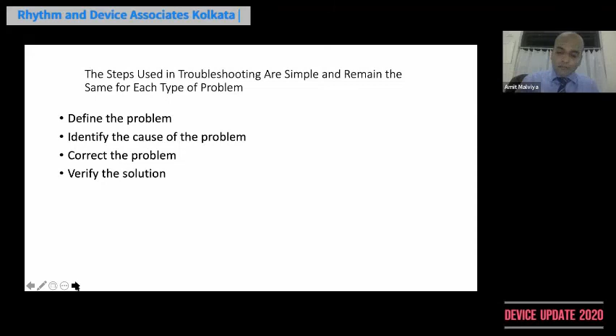For example, whether it is undersensing, oversensing. If it is undersensing, what is the problem? Whether the problem is with the generator, or it is with the lead, or with the heart of the patient, or any other problem. You correct the problem and verify the solution by obtaining the subsequent ECGs. So there are 4 or 5 potential problems which can happen during pacemaker interrogation in patients who have been implanted, either single chamber or dual chamber pacemakers.